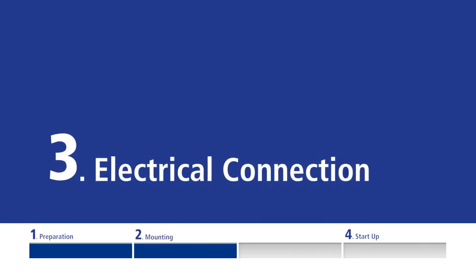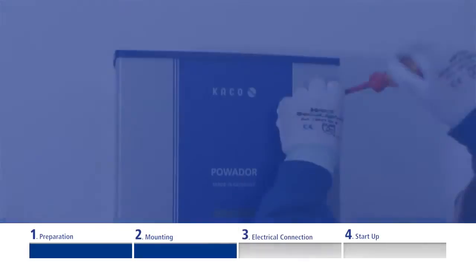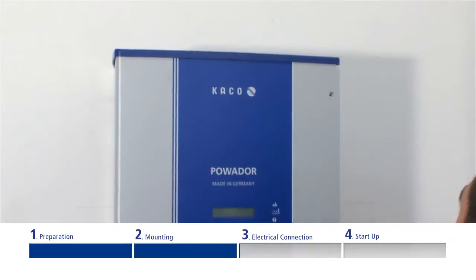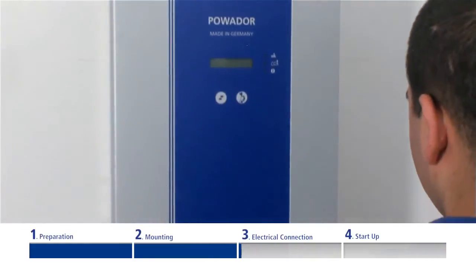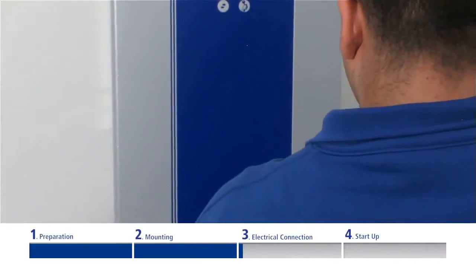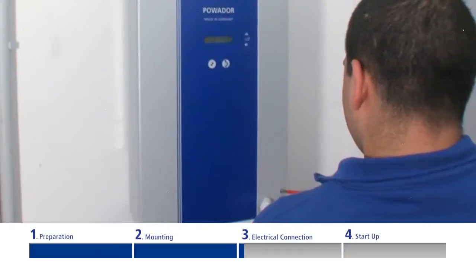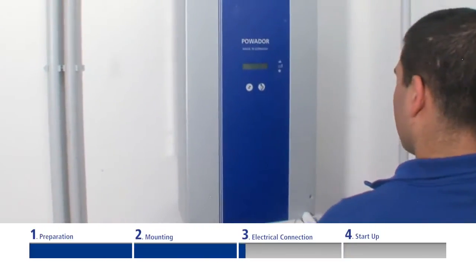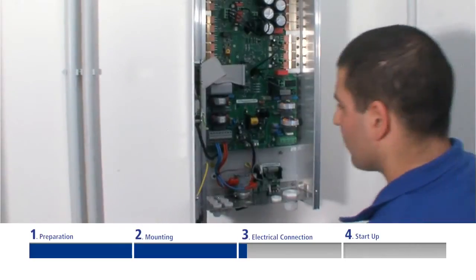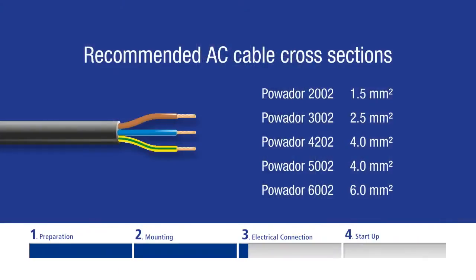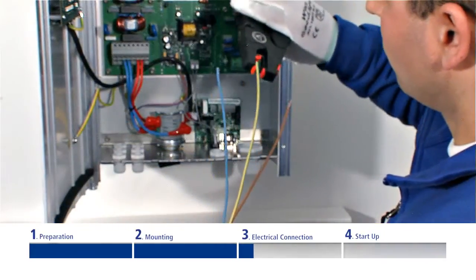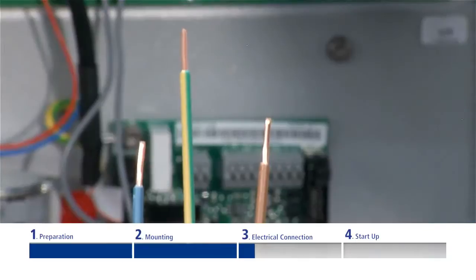The electrical connection. The inverter connection is established via PCB terminals in the inverter's connection area. The door of the housing must be opened to do this. Temporarily remove the 2 Phillips recessed head screws on the right side of the door housing. Be sure to use cables with a sufficiently large cross-section. This prevents excessive line impedance between the mains distribution board and the inverter. Excessive line impedance will lead to the inverter being switched off due to grid overvoltage.